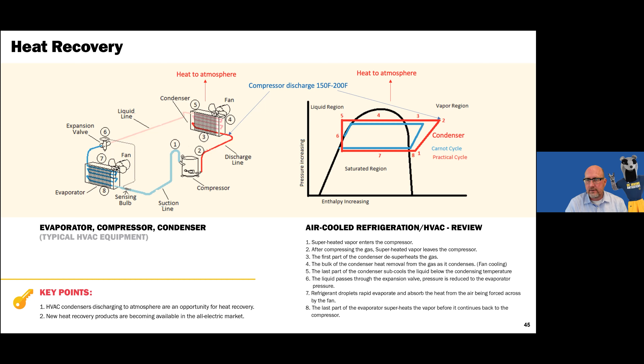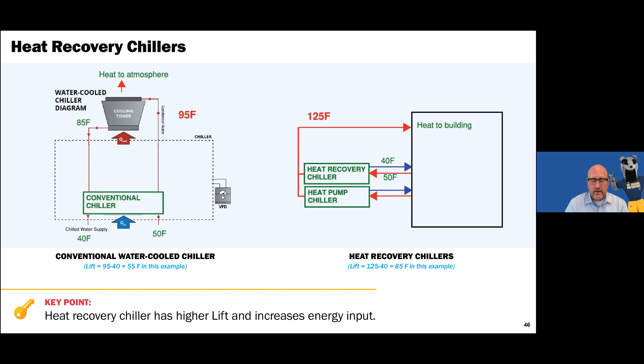So on the left-hand side, you can see that we're going to 95 degrees. On the right-hand side, we're going to 125 degrees, and the heat recovery chiller has a higher lift and increases energy input. So the conventional heat chiller has a lift of 55 degrees, while the lift of the heat recovery chiller is 85. Now, the higher lift of the heat recovery chiller means it must perform more work to meet the lift. Therefore, the heat recovery chiller at 125 degrees Fahrenheit operating temperature does use more energy, but the 125 degree temperature can be used as hospital heating supply system. While the 95 degree Fahrenheit cooling tower is more efficient, the temperature is too low to use as a useful heating source. Go ahead, Tom.